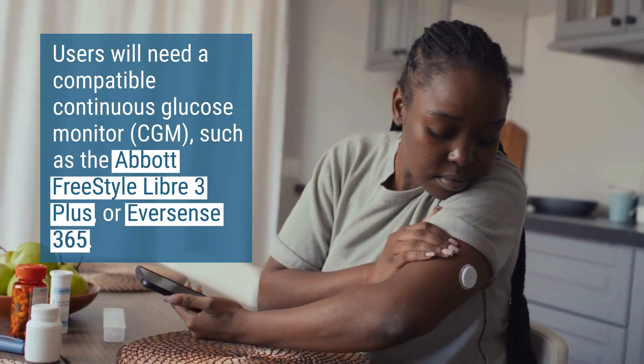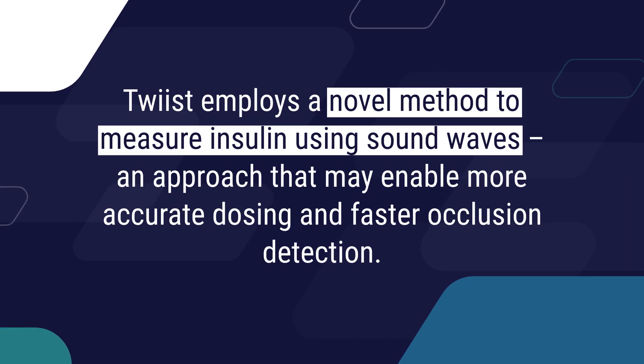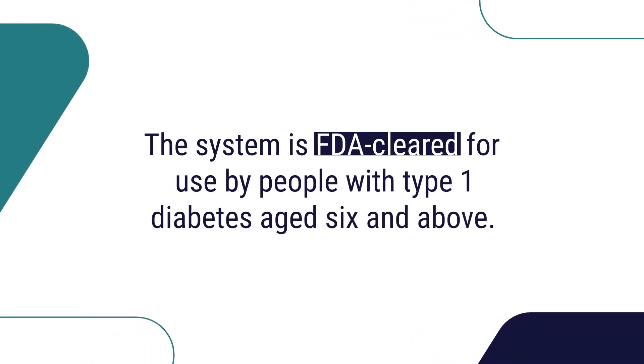Users will need a compatible continuous glucose monitor, such as the Abbott FreeStyle Libre 3 Plus or Eversense 365. Twiist employs a novel method to measure insulin using sound waves, an approach that may enable more accurate dosing and faster occlusion detection. The system is FDA cleared for use by people with type 1 diabetes aged 6 and above.